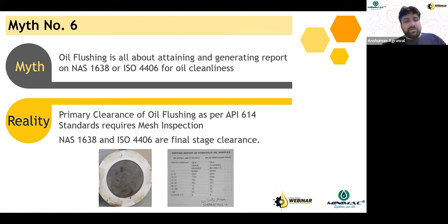This happens because NAS testing or ISO 4406 testing is done only on a 100 milliliter sample size. But the mesh inspection happens on the full flow rate, on the downstream of the flusher. Whatever system purity is to be measured, it should be measured on the downstream of the entire loop which you are flushing. So a mesh inspection on the downstream takes care of the entire flow rate passing through. And there, if the particles are at a decent enough level as per the API 614 standard, that's the stage when you can go for the secondary testing. I hope myth number six is clear: NAS 1638 and ISO 4406 must not be considered the only milestones for closing the flushing activity.